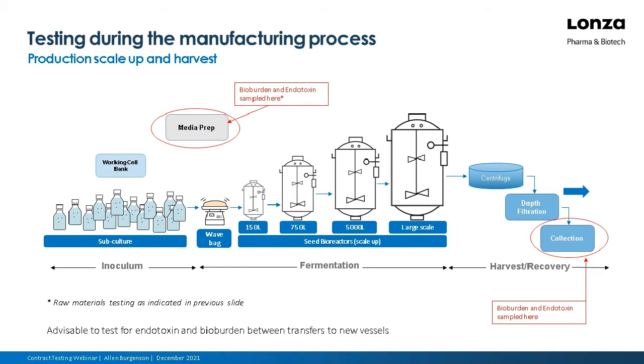So this is a schematic of a general manufacturing process, whether it be a biologic, a cell therapy product, monoclonal antibodies, or a vaccine. First, you'll start with your media prep for your seed stock, and you'll develop a working cell bank, and you'll do a lot of subcultures, and then you'll inoculate the next step up, which could be shaker flasks or a wave bag, and then you'll move up to larger fermenters as you scale up, and then you will centrifuge, depth filter, and then collect. So the two strongly suggested places to do your endotoxin testing are during your media prep, and also your bioburden and endotoxin at the end of the process. However, it's good practice to be testing between each of those process steps to make sure that you don't have an introduced contamination.